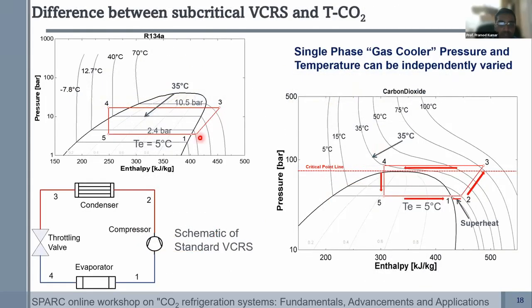So there were a lot of questions on how a transcritical CO2 cycle differs from the standard refrigeration cycle. In a nutshell, in a single answer, all conventional refrigeration cycles, including propane or isobutane or even R32, actually operate within the dome. So your entire cycle operates within the dome here. That means that when you're operating in the two-phase region, you're locked in by both temperature and pressure. You don't have the flexibility to change the pressure independent of the temperature. So depending on your ambient condition, this line 3 to 4, this pressure is going to be decided.